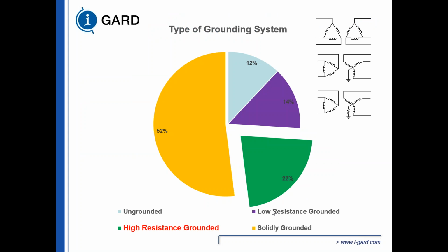So high resistance grounding system, 22% of the facilities are high resistance grounding. And the easiest thing to do is to put a resistor on a 480 volt system. You could put a 55 ohm resistor here and lower the fault current to 5 amps when you have a single phase to ground fault.